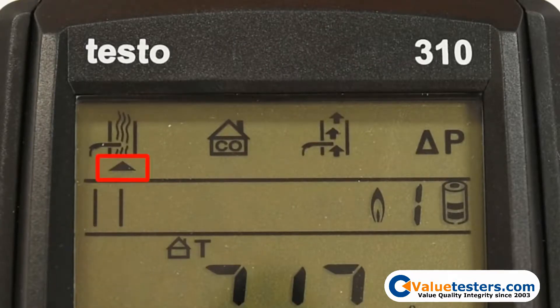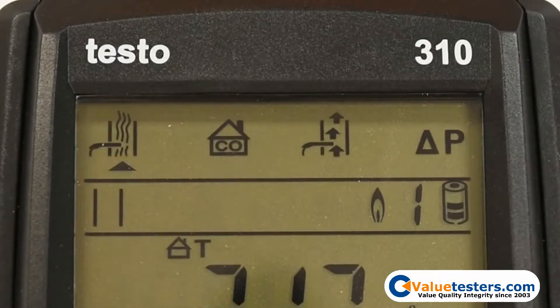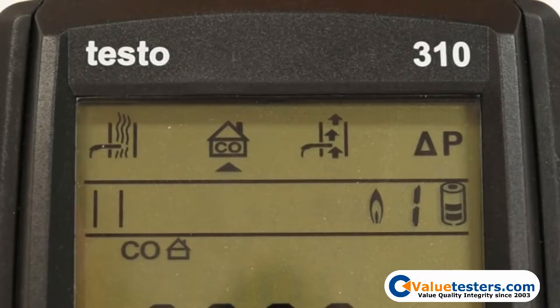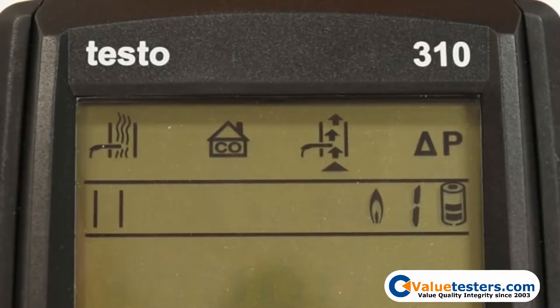The black arrow below the icon will indicate which measurement you have selected. There is a standard flue gas test, an ambient CO test, a draft measurement, and a differential pressure measurement.